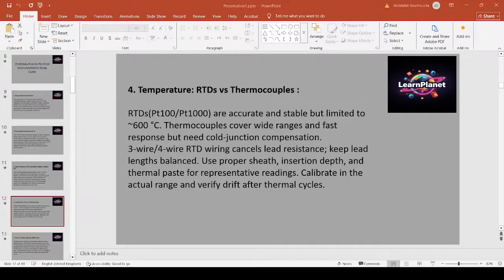RTDs, Pt100 and Pt1000, offer high stability and accuracy in moderate temperatures. Thermocouples cover extreme ranges and transient response. Use 3- or 4-wire RTD wiring to cancel lead resistance, keep lengths balanced, and use proper terminal block wiring. Thermocouples need cold junction compensation and shielding from EM noise. Choose appropriate sheath materials and ensure adequate immersion depth. Calibrate sensors in the actual process range and confirm drift after thermal cycling.